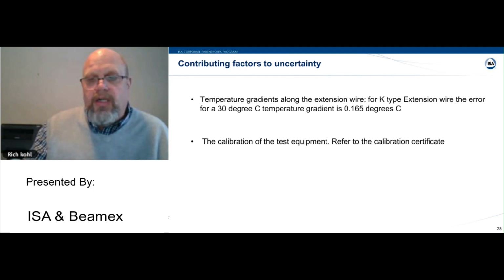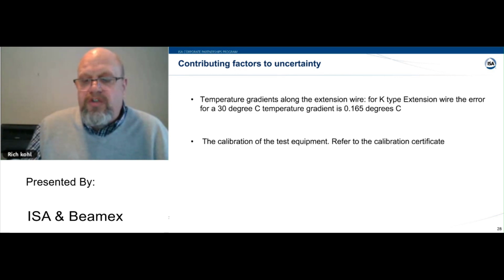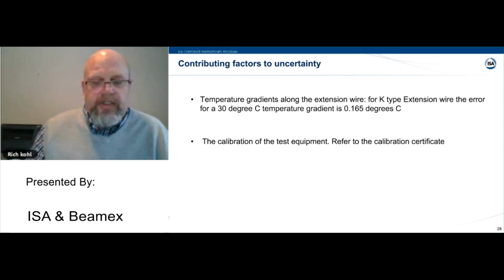You have to know all the things that go into making that a good measurement, and take that into consideration in your calculations. So then the last thing on this slide is the calibration of your test equipment. Your calibration certificate should list the uncertainty of the calibration either by stating it for each individual test point, or more than likely by making a more general statement like TUR is 4 to 1 or better for all measurements unless otherwise noted. Either way, that's a contributing factor that you need to take into consideration and combine with other contributing factors when you're trying to calculate total uncertainty.